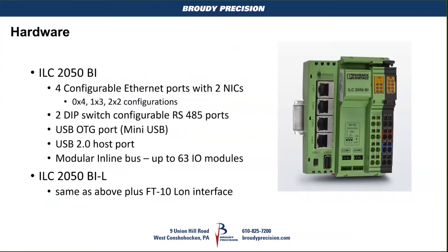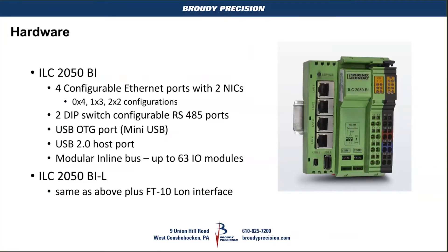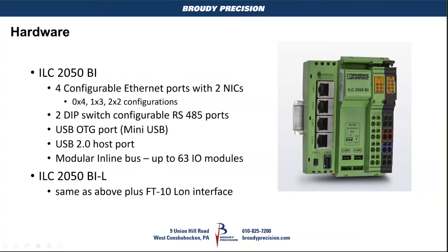If we look at the Jace itself, on the right there, that is actually the Jace. It has four configurable Ethernet ports. It actually has two NIC cards in it and you can configure it to have all four be on the same switch. You can have one by itself and three together, you can do two and two. There are two RS-485 serial ports on there. There's a mini USB that's used for getting into shell, and it has a standard USB 2.0 port as well.